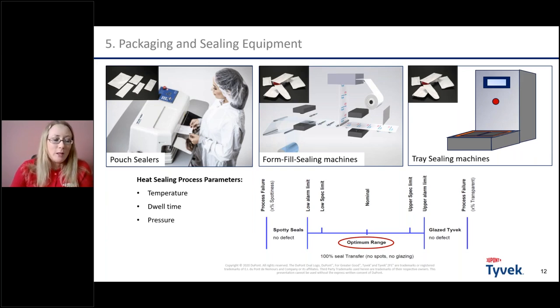So it's temperature, dwell time, and pressure usually. And now it's very important to define the optimal range of those parameters. So not only seal and validate nominal parameters, now it's important to define minimum temperature, dwell time, pressure, where you have a good and complete quality seal, and then not going so high that the seal already starts to get burned or transparent, so still a good quality seal.